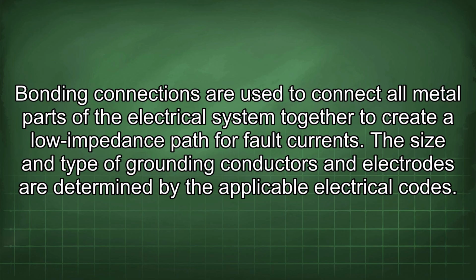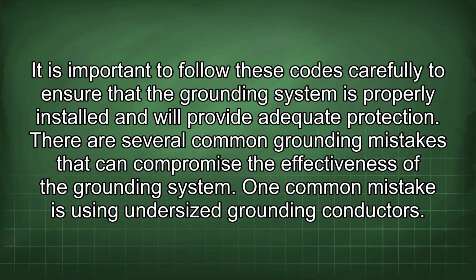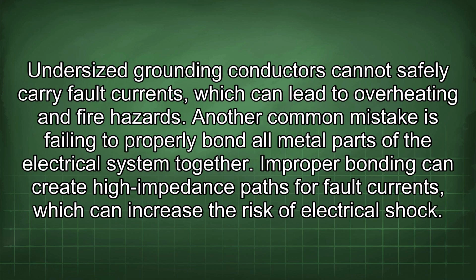Bonding connections are used to connect all metal parts of the electrical system together to create a low impedance path for fault currents. The size and type of grounding conductors and electrodes are determined by the applicable electrical codes. It is important to follow these codes carefully to ensure that the grounding system is properly installed and will provide adequate protection. There are several common grounding mistakes that can compromise the effectiveness of the grounding system. One common mistake is using undersized grounding conductors. Undersized grounding conductors cannot safely carry fault currents, which can lead to overheating and fire hazards.